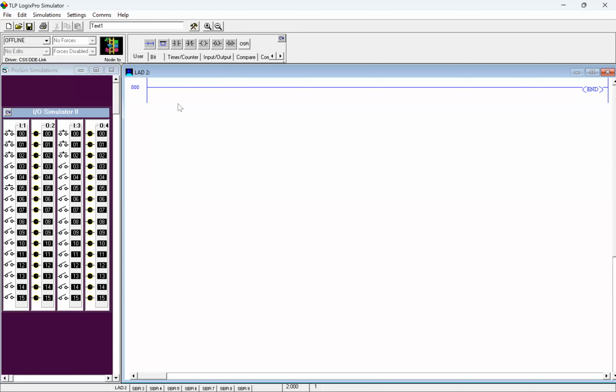In other words, this little icon is its current state without it being on. If you look at it as a normally open contact, which it's not, don't ever call it that because people will jump all over you. Really, the normal state is open, but I'm waiting for it to close, so they call it examine if closed.